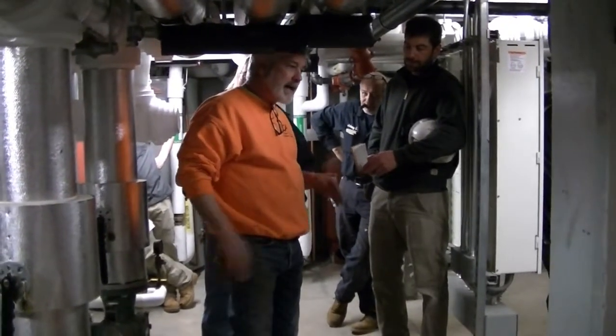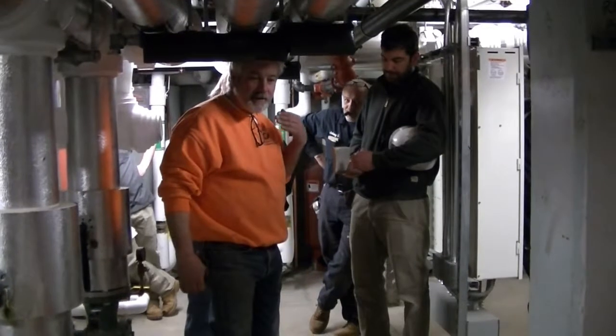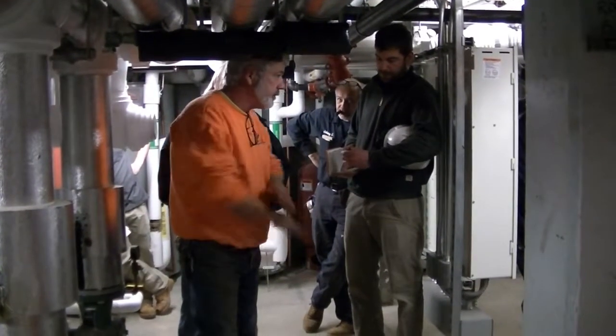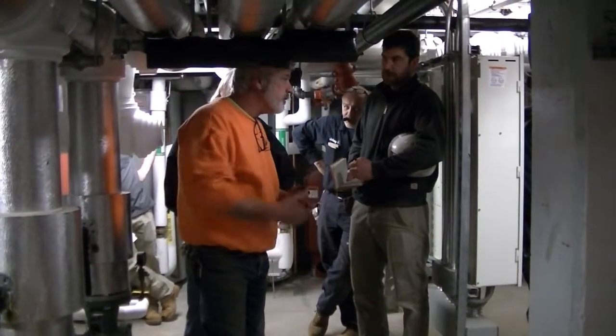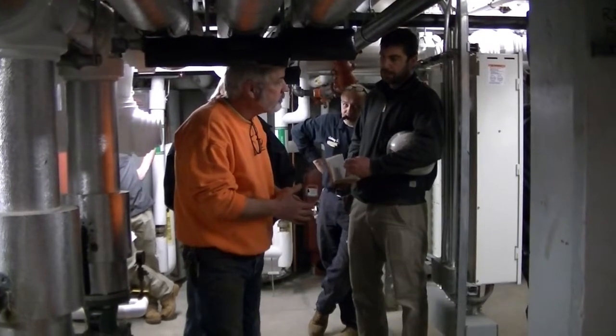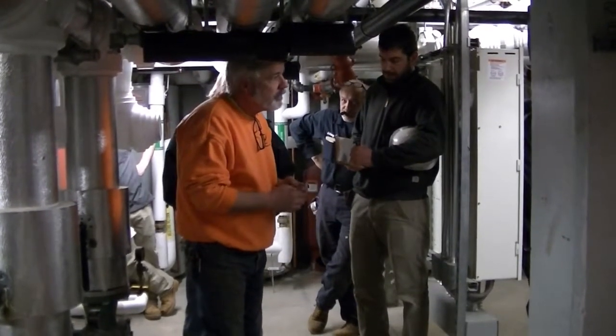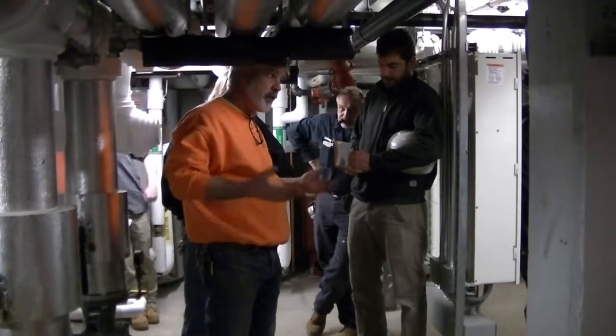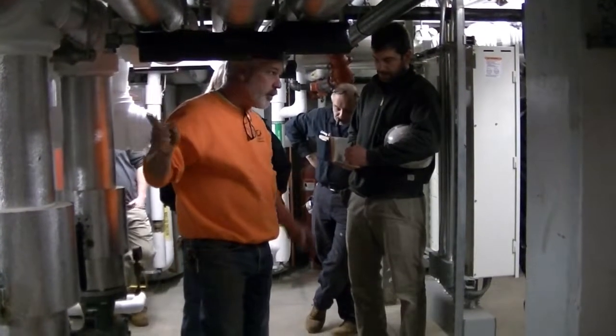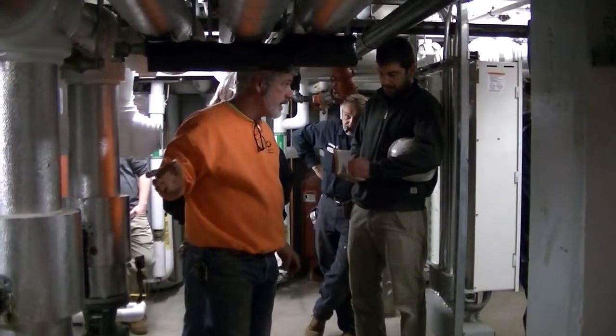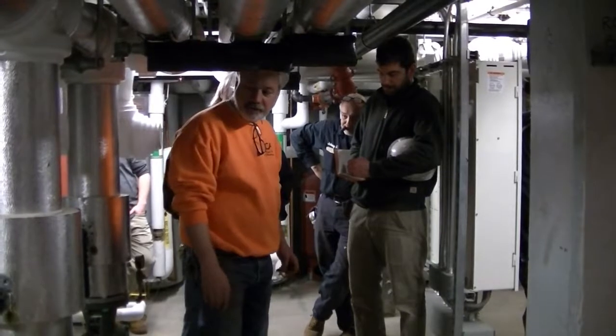Well, it actually depends on how much lift you've got. When the system's sitting dormant, you should see between 18 and 20 pounds in the system. Maybe a little more, 22, 25. If you get down to like 15, you've got a problem. Okay? There is an autofill on this system. I'll show you that later on after Kevin does this thing.